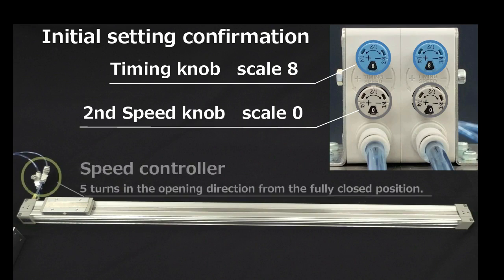The speed controllers for adjusting the first speed must be set to position 5 turns in the opening direction from the fully closed position.